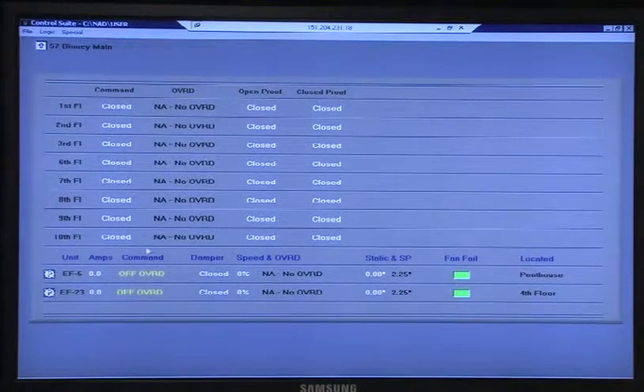So there's an open proof and a closed proof. What's the difference? They're either open or off, aren't they? Yeah, but there's two end switches on it. So the dilemma is that if it fails in mid-range, once you come off of open, it's no longer hitting the open proof end switch. Right when you come off open, it's saying that it's closed, according to what Jamie has up here. And then when it goes the other way, it's going to say that the closed is now open. So it's kind of a little confusing.